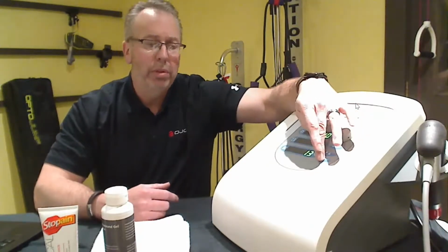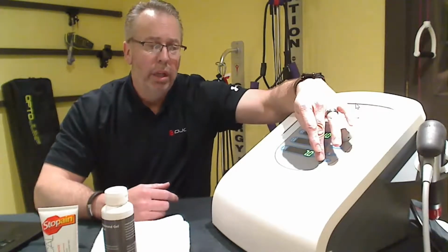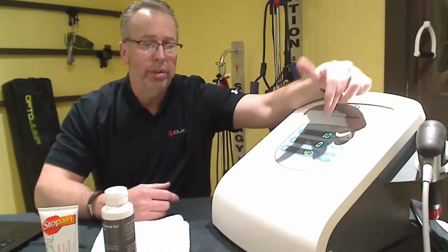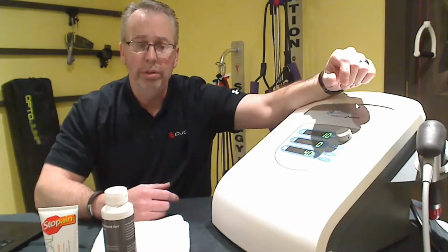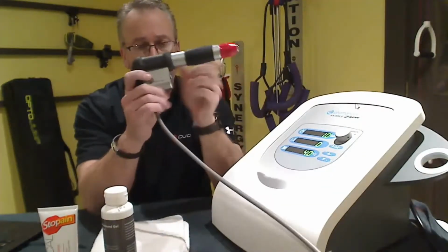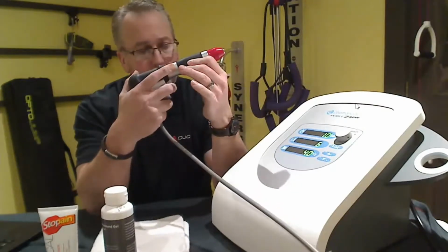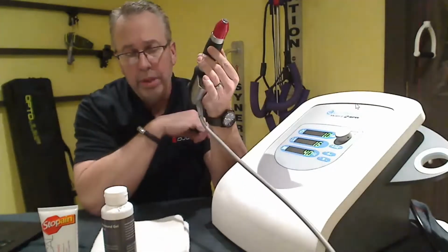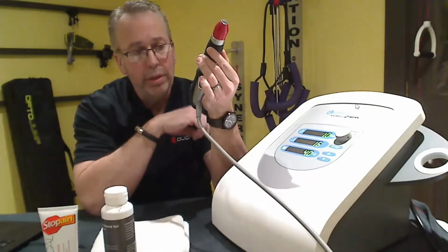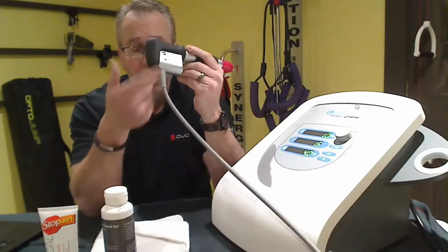And then we have the frequency setting. Normally, the first time I'm treating a patient, I'm going to start off in the low region. Often it's going to be at 1 bar and 4 hertz. Okay, so this is the applicator here. Inside is a barrel that has a projectile. You can hear that. There's a little button right here that I'm pressing that instigates the device applicator. The tube going through here increases the air going through and hits the projectile.